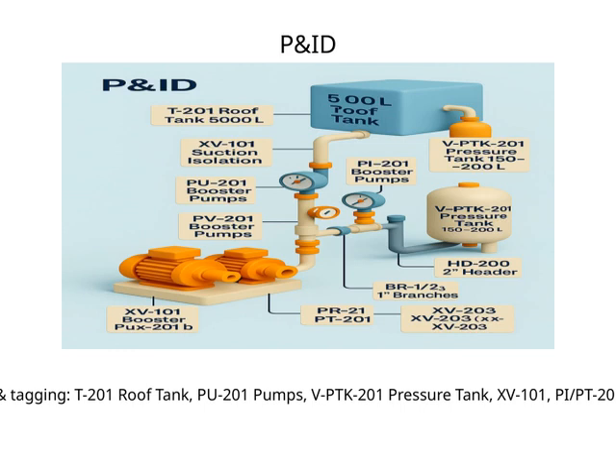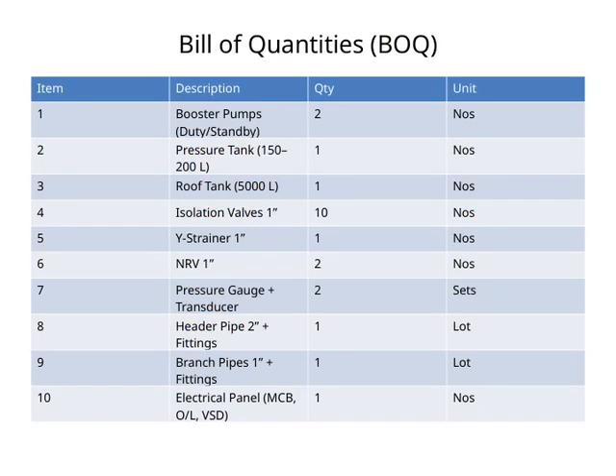system reliability and control. Let's take a closer look at the Bill of Quantities, or BOQ, which outlines all the key components needed for this project. Starting with the booster pumps, we have 2 units designated for duty and standby, ensuring reliability and continuous operation. Next, there's a pressure tank with a capacity between 150 and 200 liters, which helps maintain consistent pressure in the system. Moving on, the roof tank is significantly larger at 5,000 liters, serving as the main water storage.